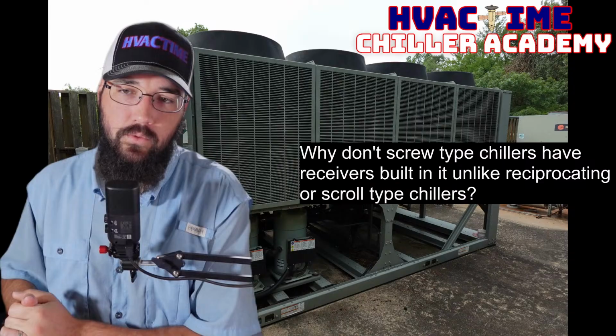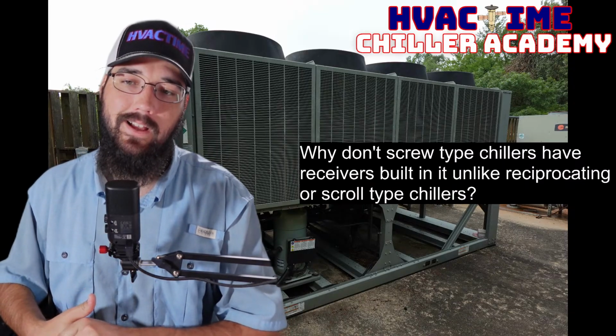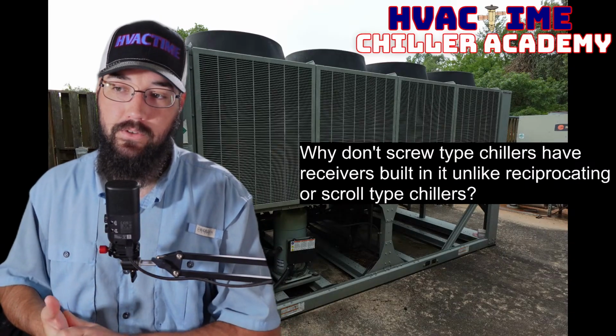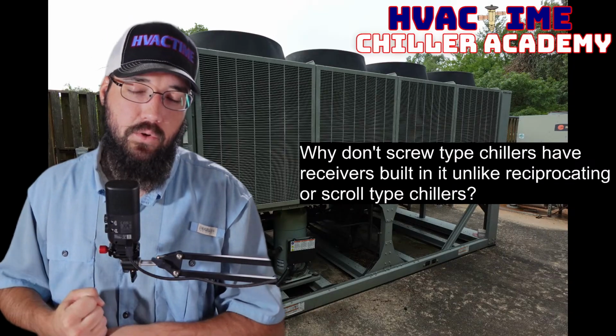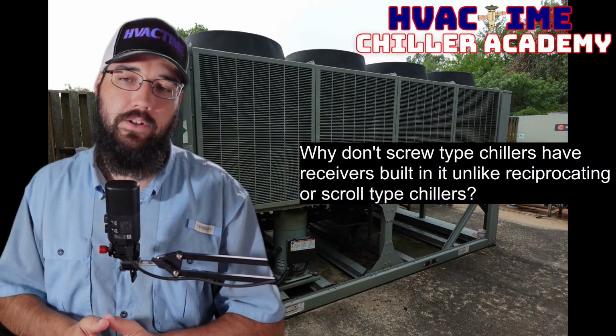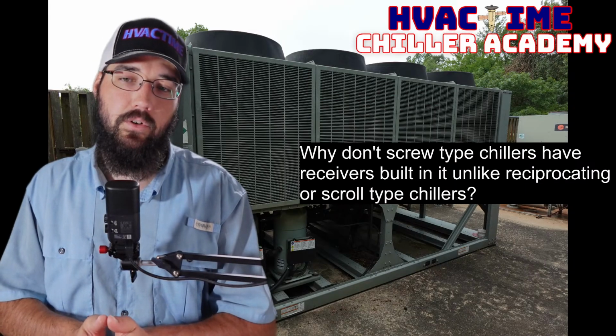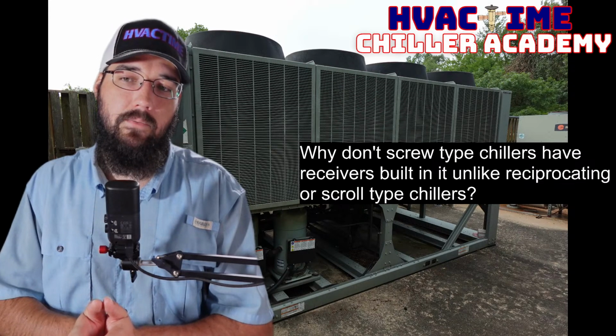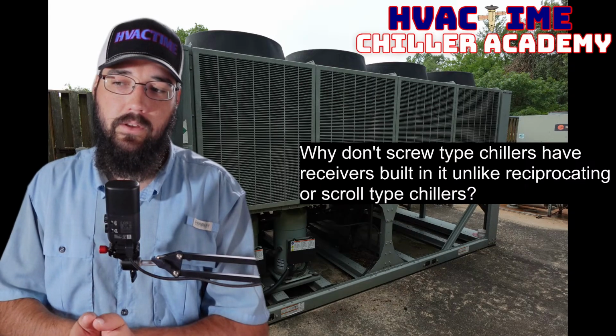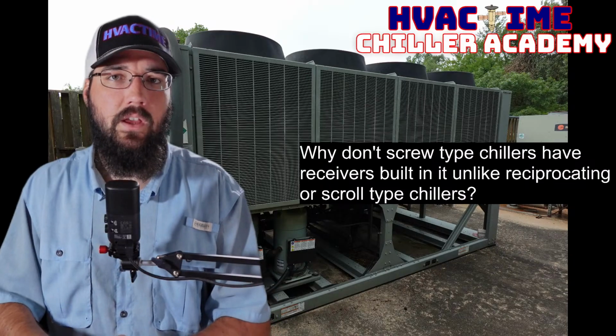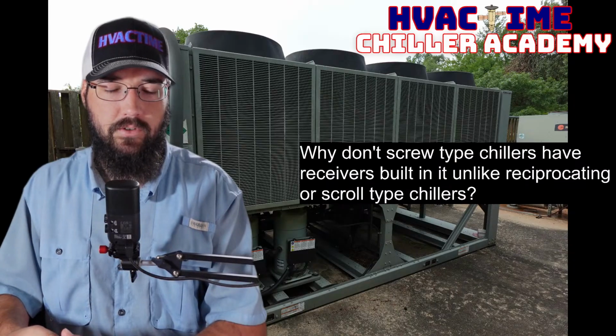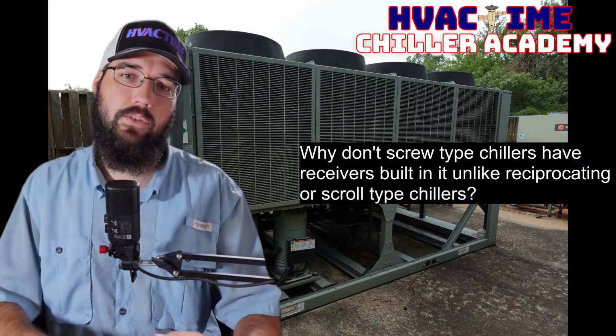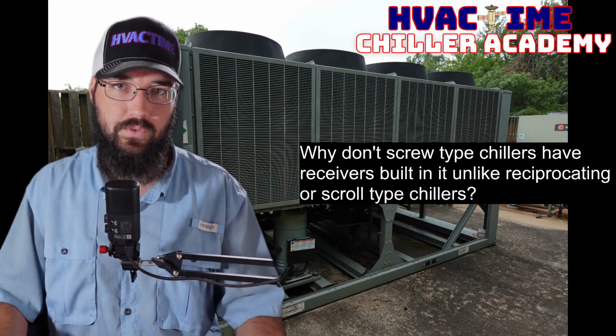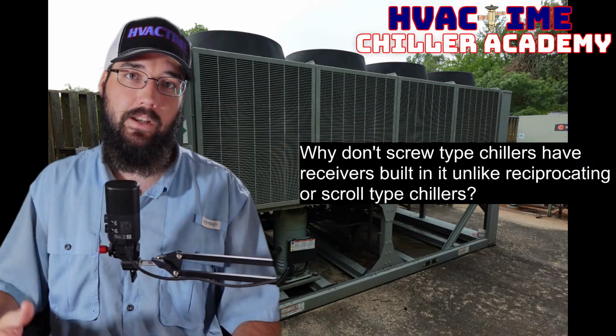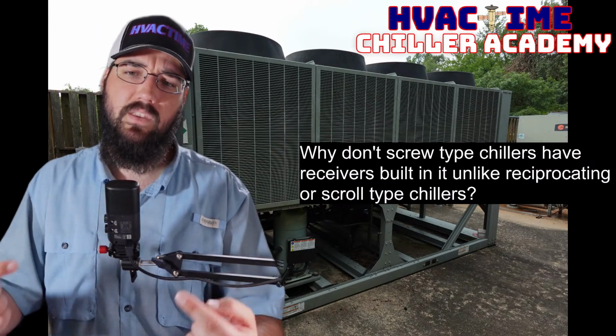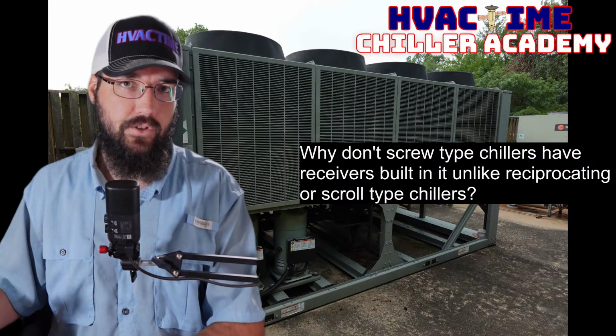All right. Why don't screw type chillers have receivers built in, unlike reciprocating or scroll type chillers? Most of the scroll and reciprocating chillers you come across do have liquid line receivers. That would make me think you're probably dealing with more of a small process chiller. Those styles are a little different from the larger standard heavy commercial chiller. The one behind me is an example of a CGAM, a Trane air-cooled scroll. It does not have a liquid line receiver, and I would say most of that particular sector of chillers typically don't.